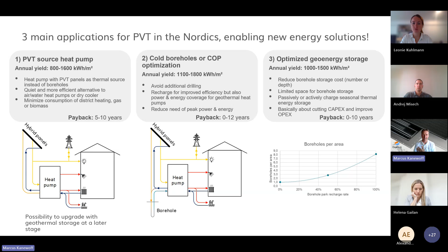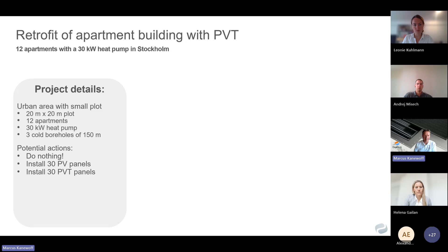So how does the PVT affect the system? If we go a little bit into detail, this is a real project. It's in Stockholm, a small multifamily house with a heat pump and 3 cold boreholes of 150 meters each. So the board has to decide between doing nothing, install 30 PV panels, or 30 PVT panels. And the blue line shows the existing temperature in the boreholes. And as you can see, 6-7 degrees, 3-4 months, that's the breaking point where the heat pump couldn't run. So it has to go full electricity.